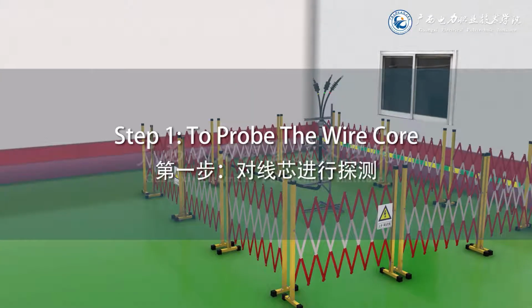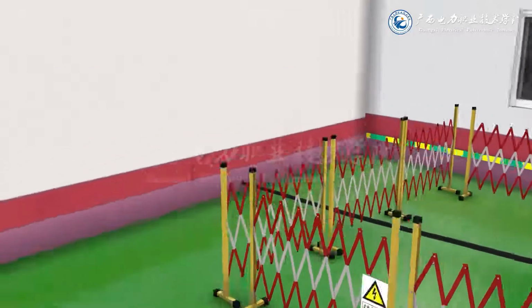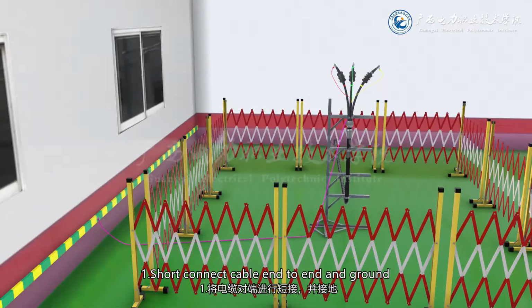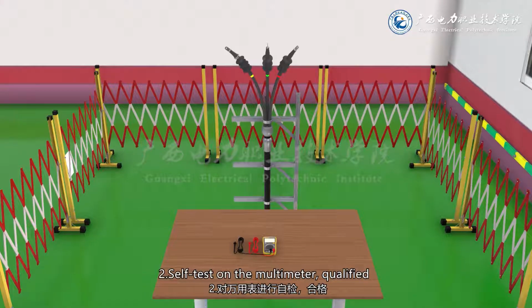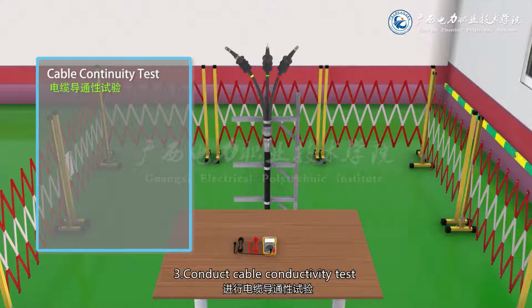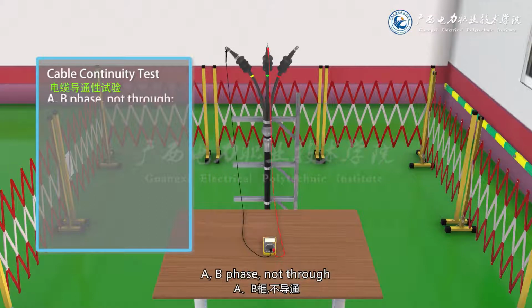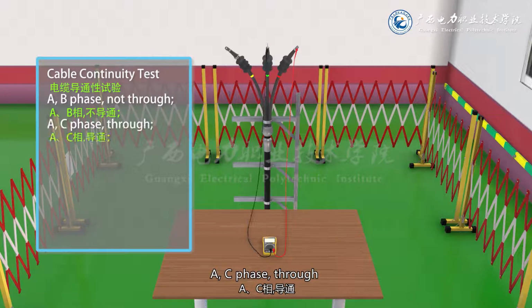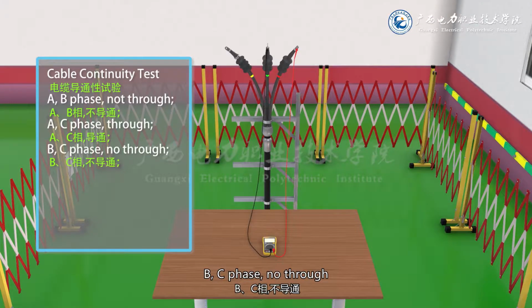Step 1. Probe the wire core. 1. Short-connect the cable end to end and ground it. 2. Self-test the multimeter; it is qualified. 3. Conduct the cable conductivity test. A, B phase: not through. A, C phase: through. B, C phase: not through.